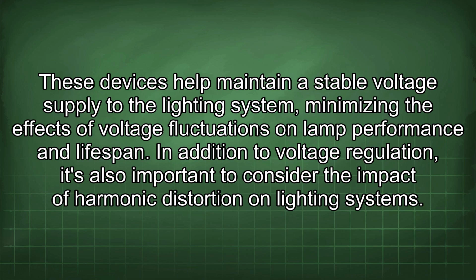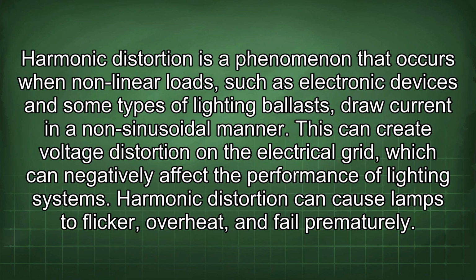performance and lifespan. In addition to voltage regulation, it's also important to consider the impact of harmonic distortion on lighting systems. Harmonic distortion is a phenomenon that occurs when nonlinear loads, such as electronic devices and some types of lighting ballasts, draw current in a non-sinusoidal manner. This can create voltage distortion on the electrical grid, which can negatively affect the performance of lighting systems. Harmonic distortion can cause lamps to flicker, overheat, and fail prematurely.